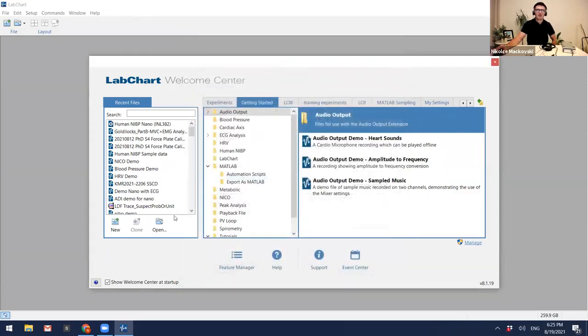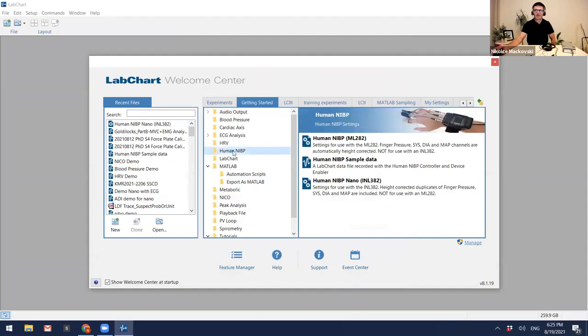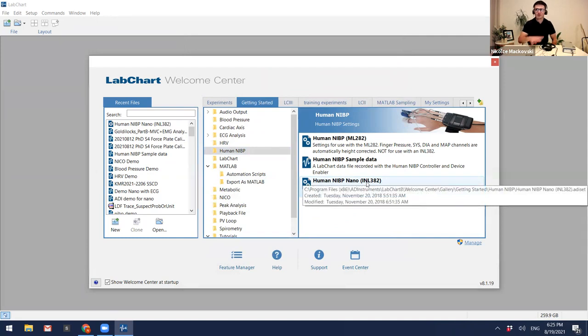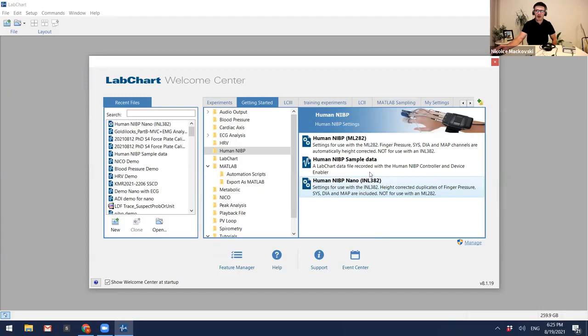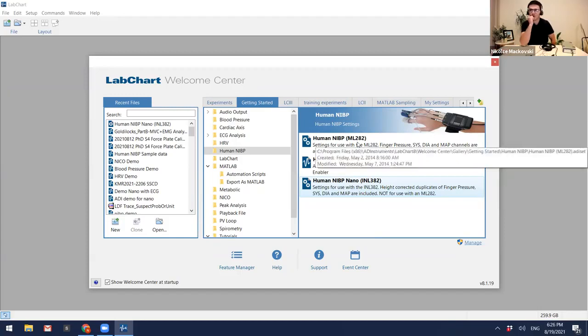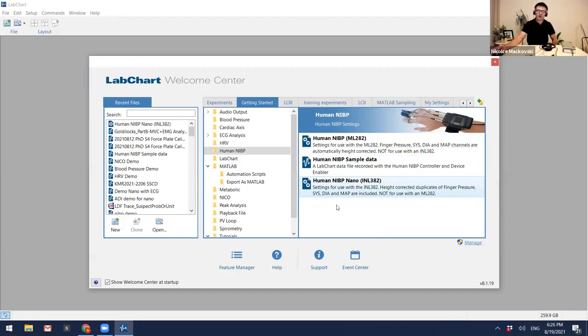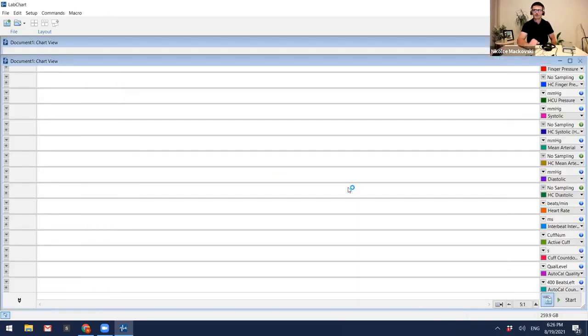Once that's done, you could click on New and start recording, but those aren't actually going to have the parameters for HCU selected. So what we need to do is make sure under Getting Started, we click on Human NIBP, and then we go to Human NIBP INL382. So that's the product code for this particular Nano. Here's actually the settings file if you have the older version, the ML282. So what we do here is we're going to open this up.